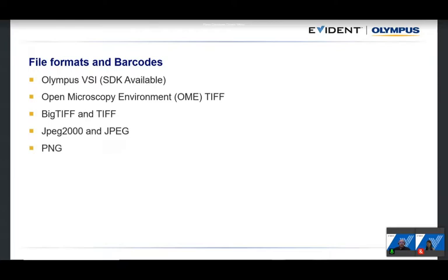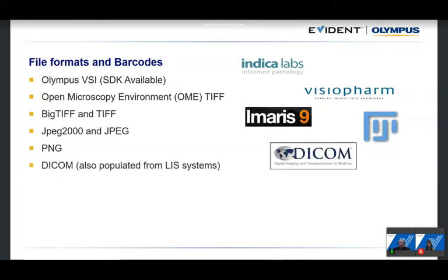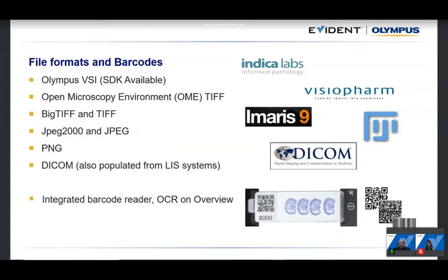For workflow compatibility, images can be saved in the native Olympus VSI format, but you can also export to OME-TIFF, BigTIFF, JPEG 2000, JPEG, and PNG. This ensures compatibility with the majority of analysis packages. You can also create DICOM standard images and import data from a laboratory information system. The system reads barcodes from slides, automatically saving images with barcode information so they can be routed to the correct analysis software downstream.